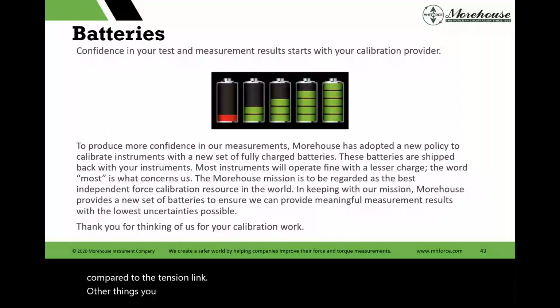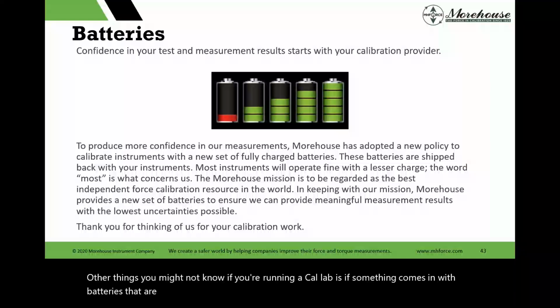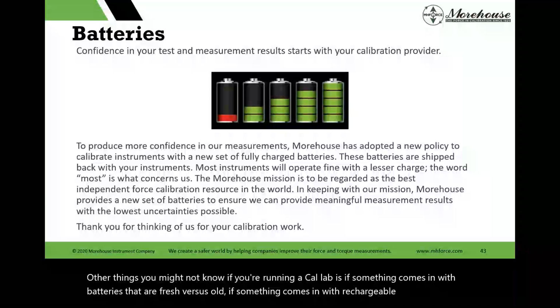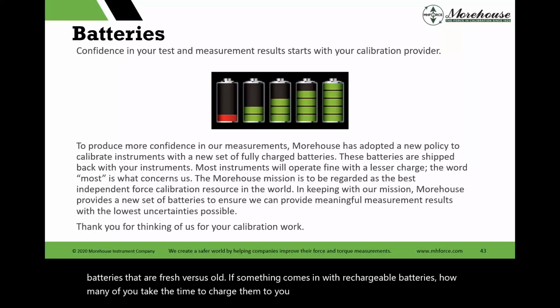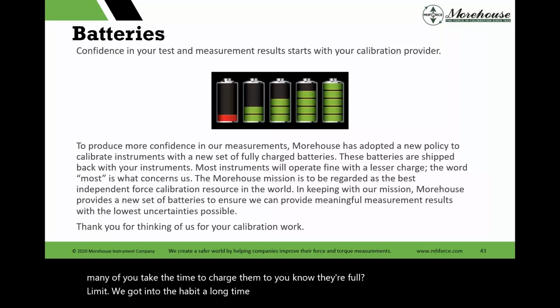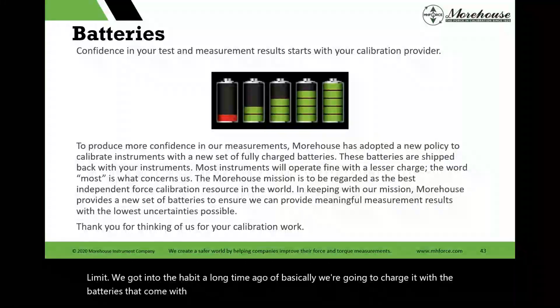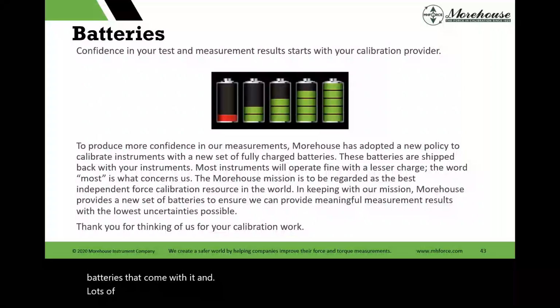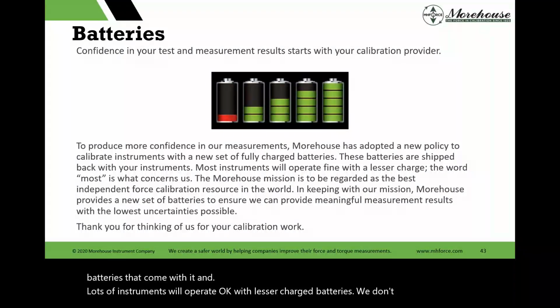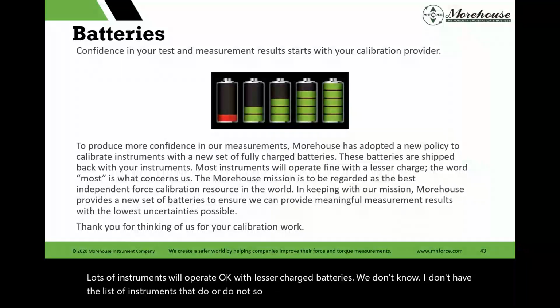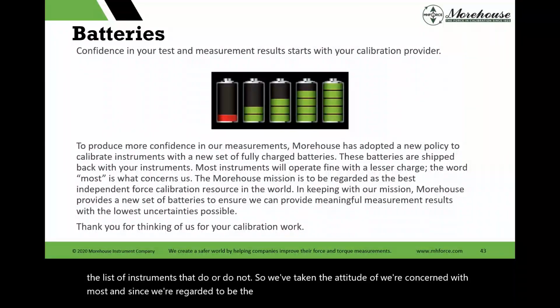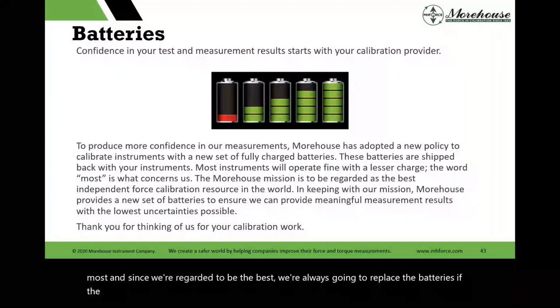Other things you might not know if you're running a Cal Lab: if something comes in with batteries that are fresh versus old, if something comes in with rechargeable batteries, how many of you take the time to charge them to their full limit? We got into the habit a long time ago of basically charging it with the batteries that come with it, and lots of instruments will operate okay with lesser charged batteries. We don't know. I don't have the list of instruments that do or do not. So we've taken the attitude of we're concerned with most. And since we're regarded to be the best, we're always going to replace the batteries if the batteries need replaced.